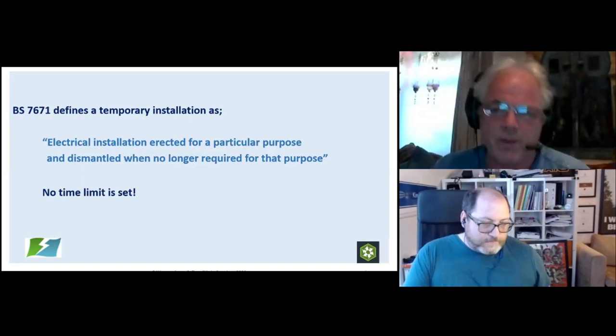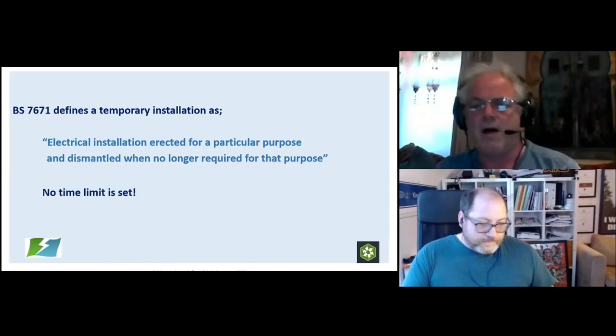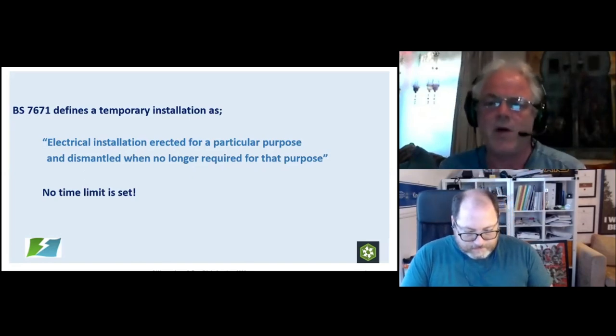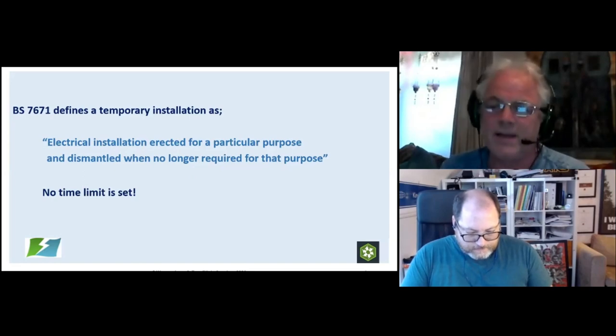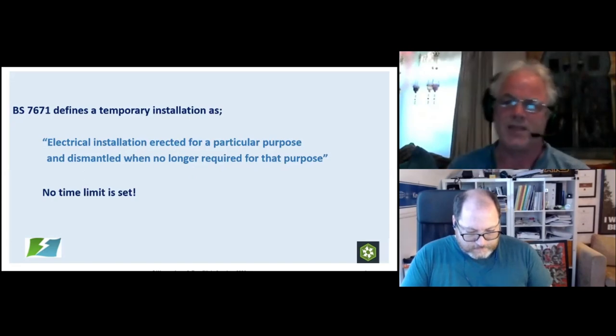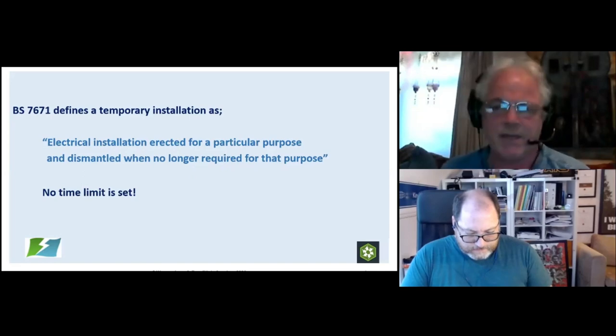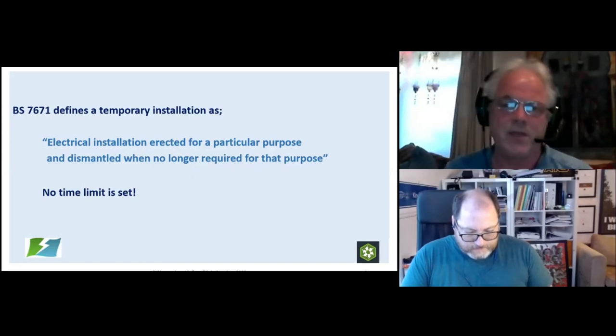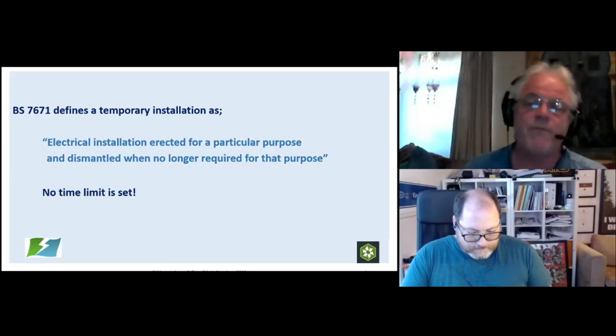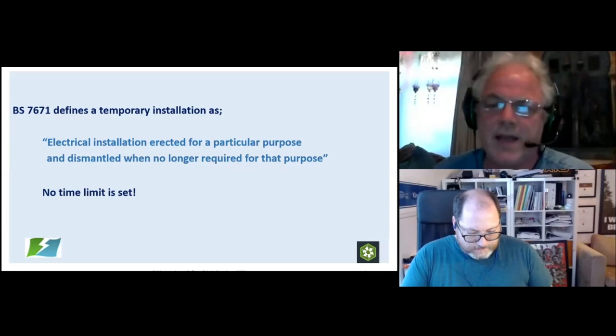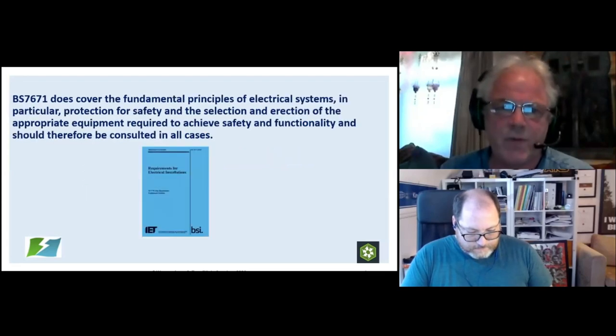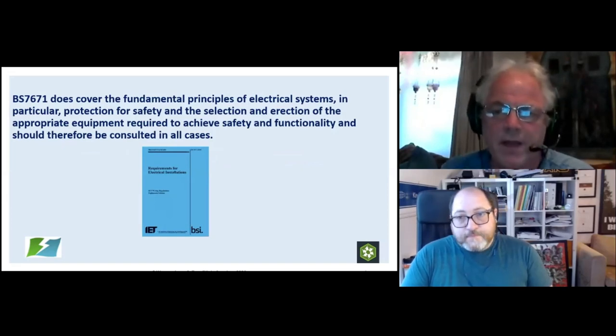Generally, with a temporary system, when we do the inspection and testing after the installation, we're looking at a finite period of time before it is required to be tested and inspected again. Remember, with temporary electrical systems, there's quite often a lot of dynamic stuff going on. Things are getting moved, added, changed. If there's any significant change or addition, it will need to be inspected and tested again. But generally, a temporary system is put in for a particular purpose and then pulled out again. That's what BS7671 does. It covers the fundamental principles, protection, safety, selection, erection, etc. But it doesn't cover the nitty-gritty of the temporary system.